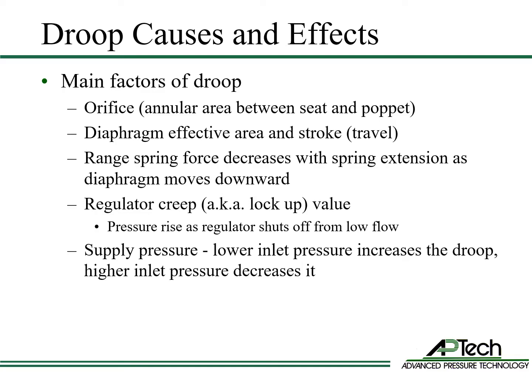Regulator droop is caused by several factors. A larger orifice, diaphragm, and diaphragm stroke reduce droop. The adjustment range spring's force decreases with spring extension as the diaphragm moves downward, which increases droop. When a regulator transitions from low flow to no flow, the regulator creeps, or locks up, and the outlet pressure increases slightly above set point, increasing droop. Finally, higher supply pressures decrease droop, and lower supply pressures increase droop, as we will demonstrate in the next slide.